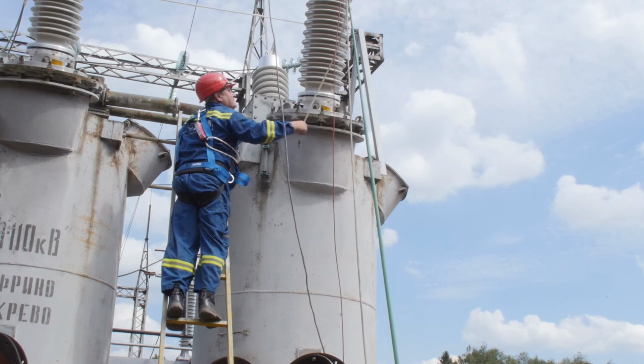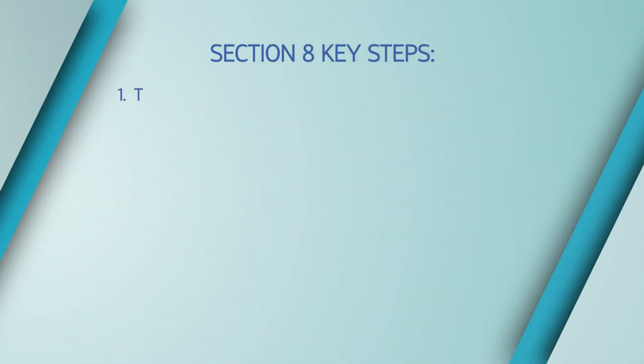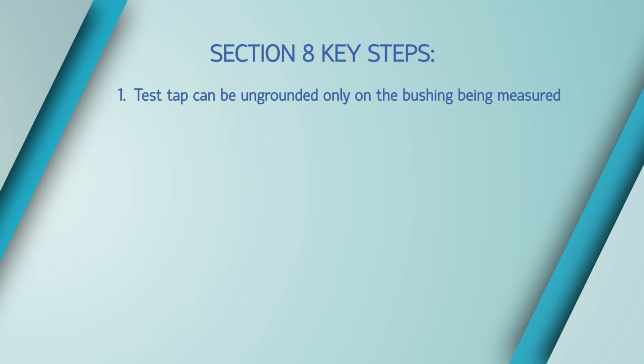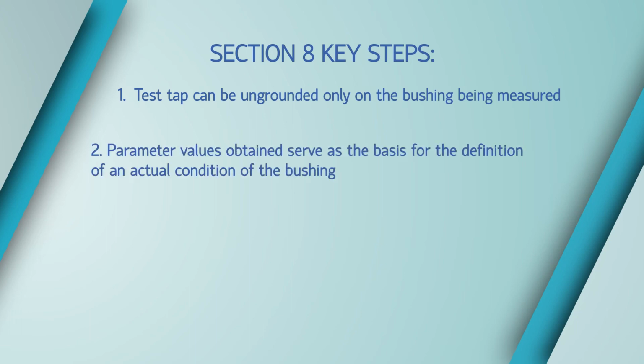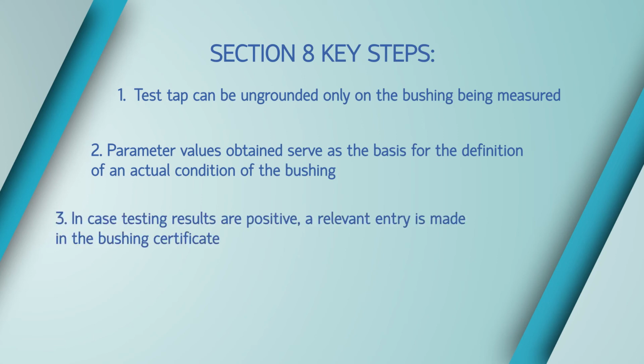Thus, we have reviewed post-installation tests. Let us repeat the key steps. Test tap can be ungrounded only on the bushing being measured. Parameter values obtained serve as the basis for the definition of an actual condition of the bushing. In case testing results are positive, a relevant entry is made in the bushing certificate.